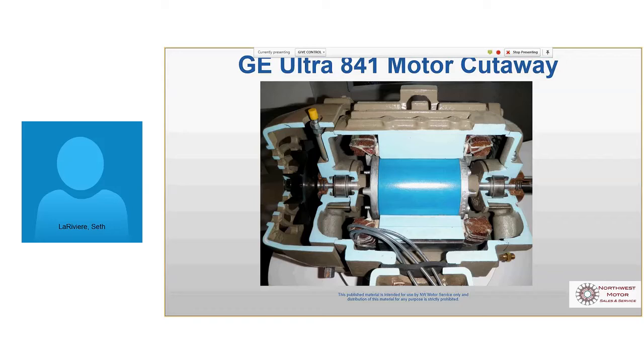Now, the part of the winding that's inside the slot here is pretty well held in place by the slot that it lives in. It doesn't get to move around a whole lot. But out here on the end, you see a lot of flex. And we've actually got a slide that shows that in slow motion, how much flex is happening there. The downside to that is, as these flex over time, every one of these wires is insulated, and if you get that movement, you get some abrasion, and you can wear away the insulation on every strand of those wires. If those insulations wear, then you've got a short. So that's the beginning of the end, as they say. So the bracing is another great feature on this.